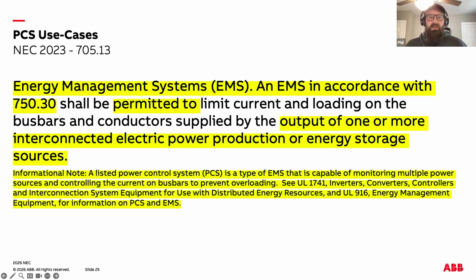But Section 705.13 was introduced as a way to address exactly that challenge. It provides a compliant method for connecting load-side power production sources, like PV or energy storage, even when their contribution would otherwise exceed the sizing limits established in 705.12. In other words, 705.13 opens the door for smarter, controlled interconnections that don't automatically force a service upgrade, and it's this concept that evolves significantly in the 2026 NEC.